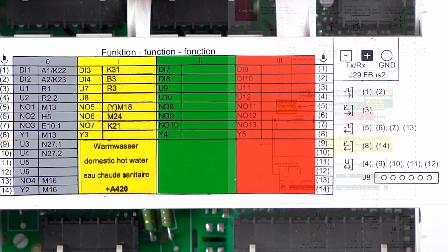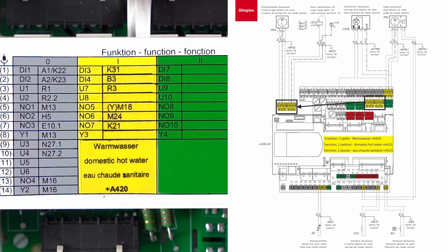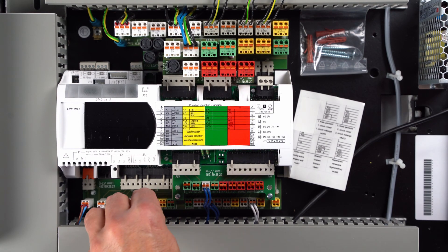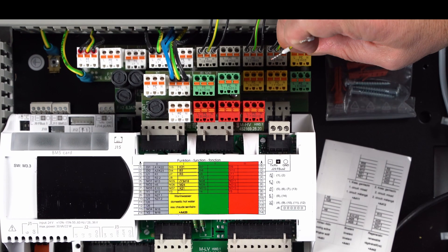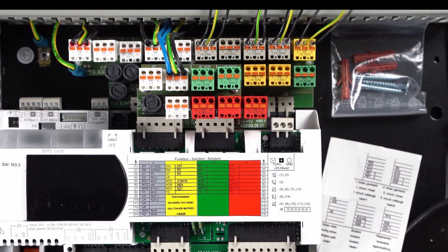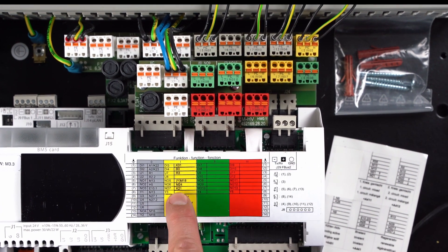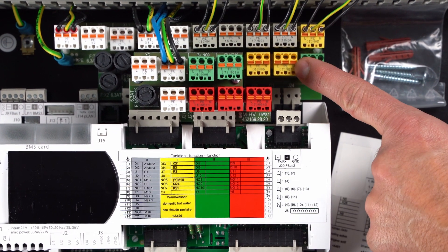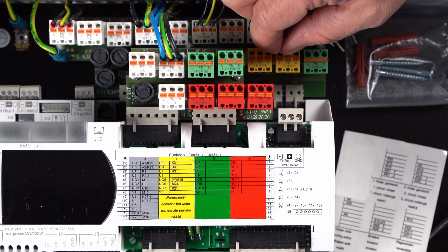Inputs and outputs for the hot water function are defined for each connector of the yellow function block, as described and assigned in the quick installation guide supplied. The hot water sensor R3 is clamped onto the yellow plug 3, U7. The switching valve or the circulation pump M18 is clamped to the yellow connector 5, NO5, and the relay K21 for the flange heater is to be clamped to the yellow connector 7, NO7.